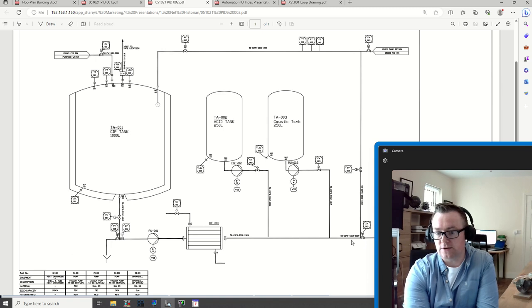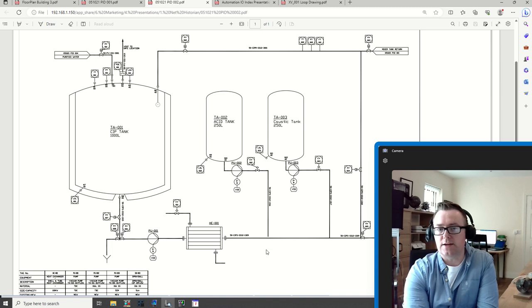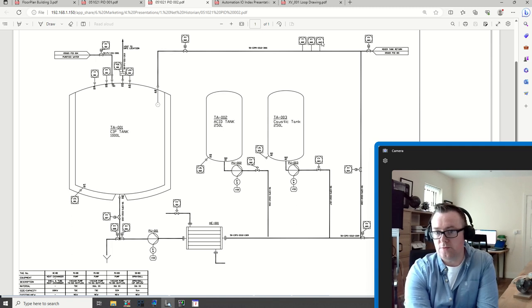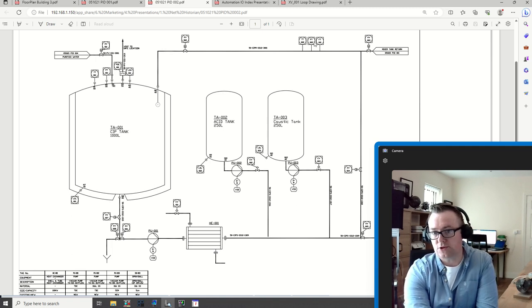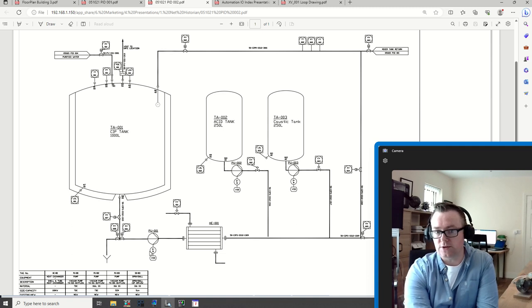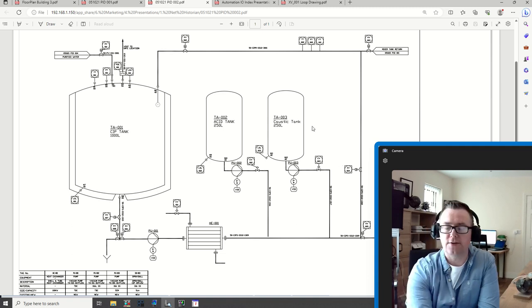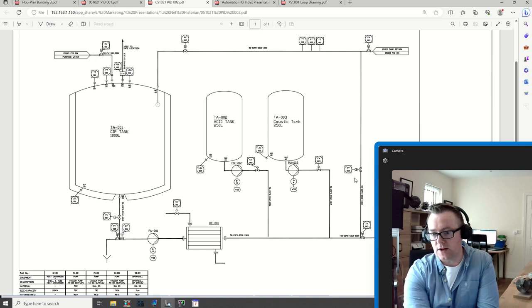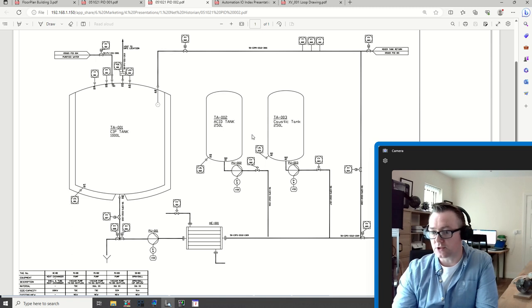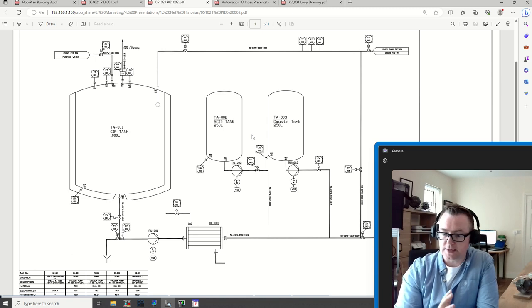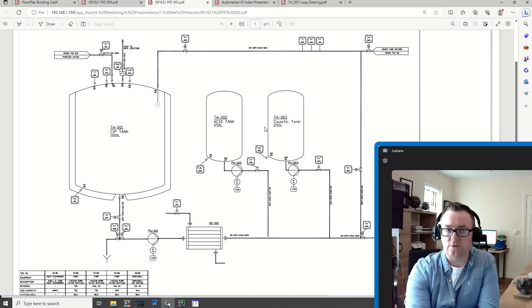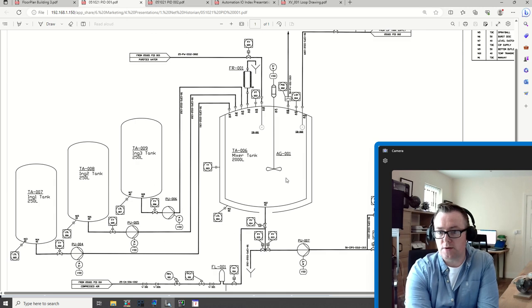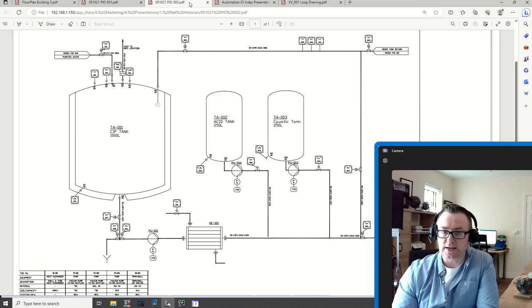These two particular valves stay closed, and we have a heat exchanger here. We have a flow meter, a pressure sensor, and a temperature sensor up here. The tank wants to be able to recirculate to clean itself. We want to have this particular valve closed, and then we can add certain ingredients to the wash. We'll be able to monitor this from our DeltaV program.